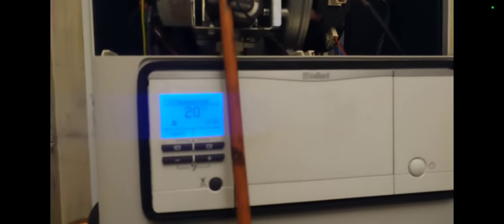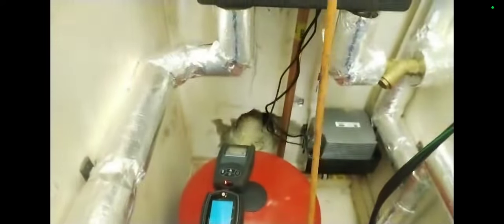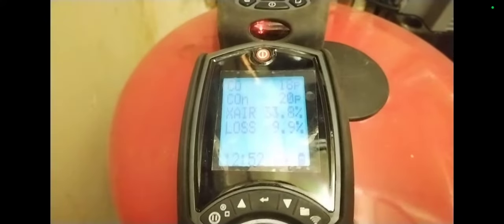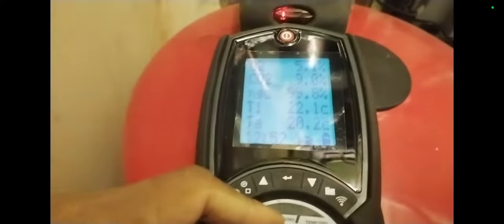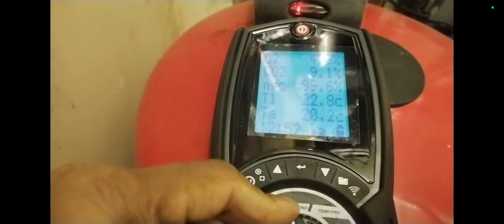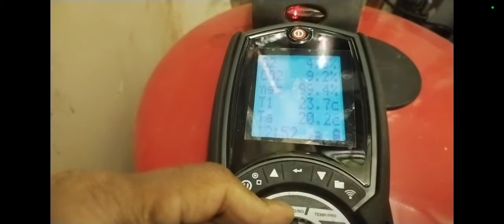So I'm going to get my multimeter, pump, and analyzer ready. Get the pump running. Remember to turn the pump off when you're not using it. It's good when you can connect up the gauge to the working pressure at the same time, so you can see what the working pressure is, or sometimes if you're doing burner pressure, so you can just have it all printed out on the same printout.